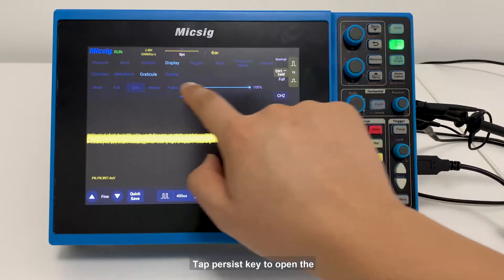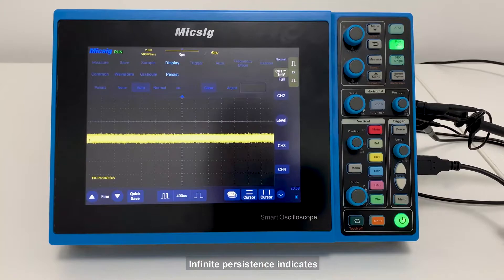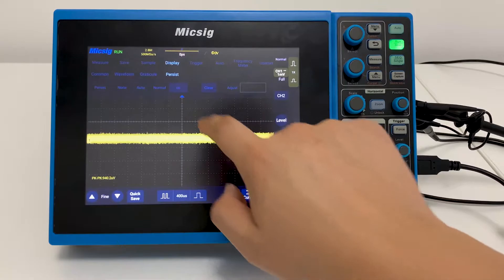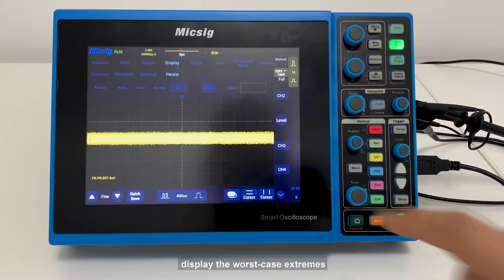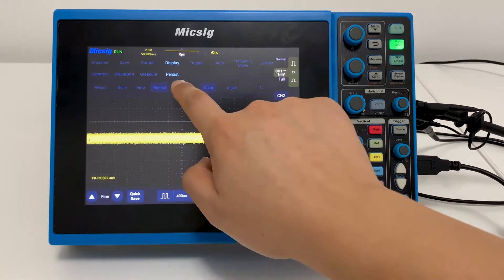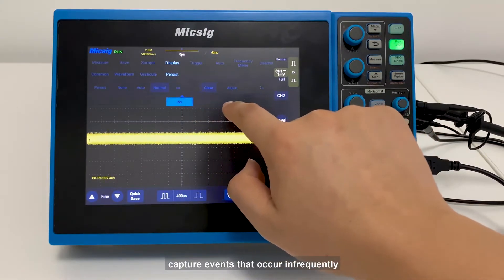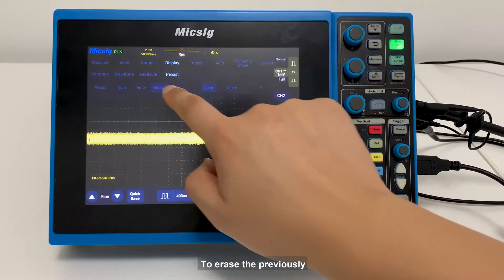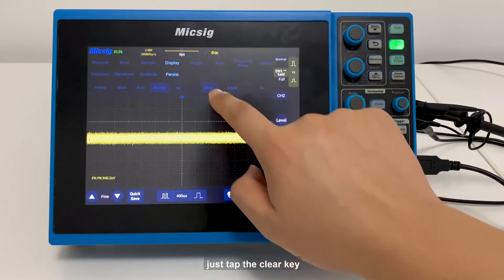Tap the Persist key to open the persistence settings menu. Infinite persistence means never erasing the results of previous acquisitions. It can be used to measure noise and jitter, display worst-case extremes of varying waveforms, find time variations, and capture events that occur infrequently. A set persistence time is also available. To erase previously acquired results from the display, just tap the Clear key.